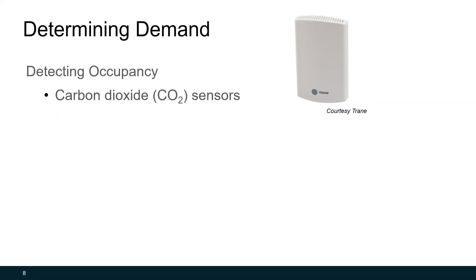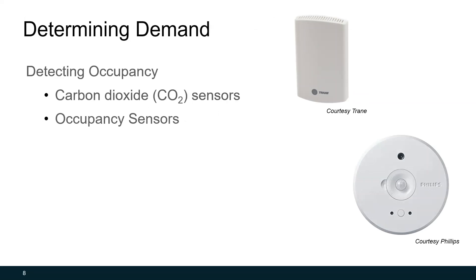The first step to implement demand-controlled ventilation is determining demand. To determine demand, we can use a number of sensors that detect occupancy. We can use carbon dioxide sensors or we can use occupancy sensors. Carbon dioxide sensors are most commonly used for DCV — they're analog sensors. Occupancy sensors are binary sensors; their limitation is they can only detect if a room is occupied, but they can't tell you how many people are in the room. Carbon dioxide sensors, by detecting CO2 which we all breathe out, can provide a rough estimate of the number of people in the space.